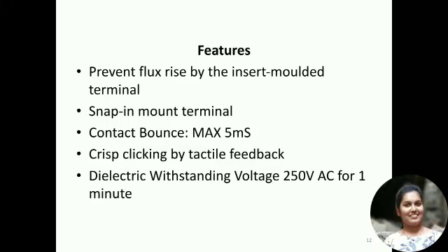And the second feature for push button switch is the snap in mount terminal, a special feature for push button switches. The contact bounce is up to a maximum of 5 millisecond, and a crisp clicking by the tactile feedback is there for push button switches. Dielectric withstanding voltage, this is the main point, is up to 250 volts AC for 1 minute.